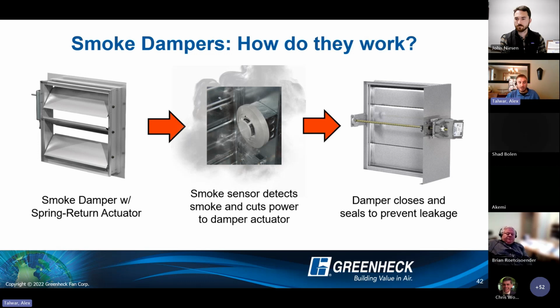In terms of how they work, a multi-blade damper with a spring return actuator is connected to some type of smoke detector or detection system. Once the system detects smoke, it sends a signal to the actuator, actually cuts the power to the actuator, and then there's a spring mechanism in there that automatically closes that damper and seals up to prevent the spread of smoke throughout the building.